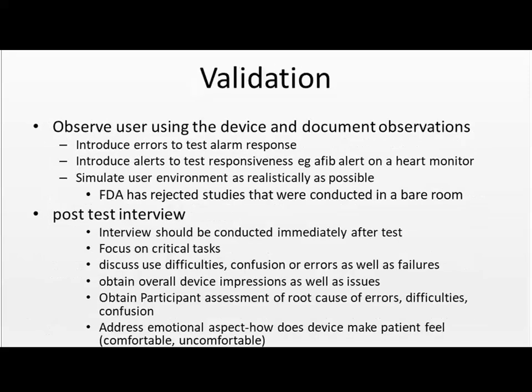Okay, validation. As I said, we're going to observe the user using the device and document the observations. As part of that test, we'll introduce errors to test alarm response, if that's appropriate. We'll introduce alerts to test responsiveness, for instance, afib alert on a heart monitor.